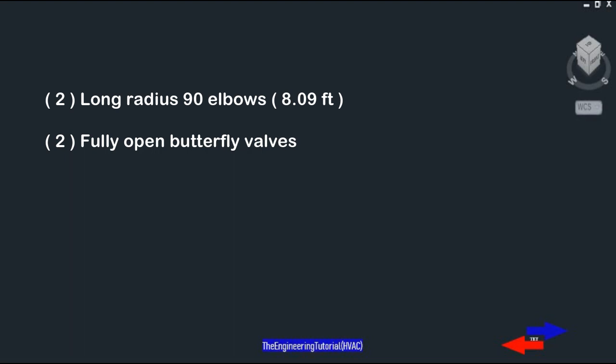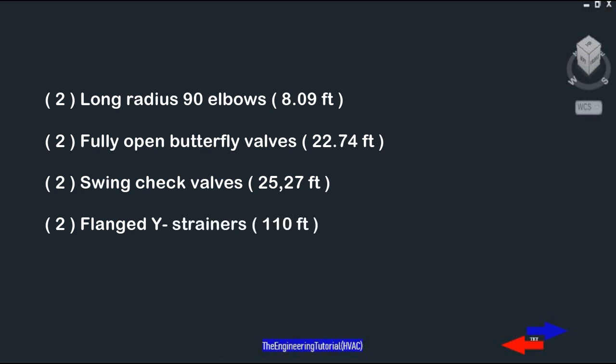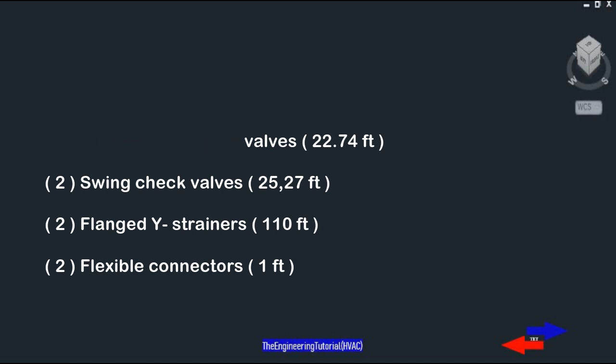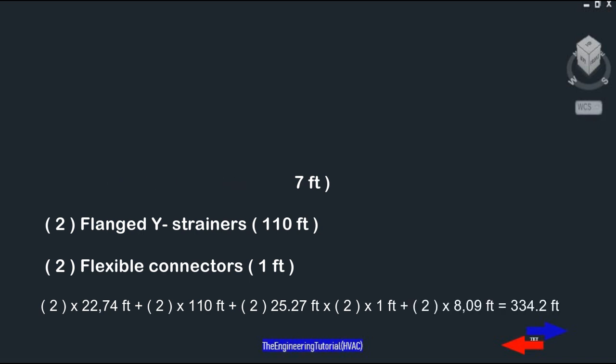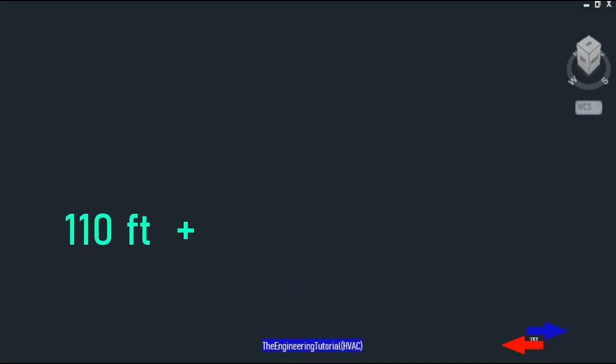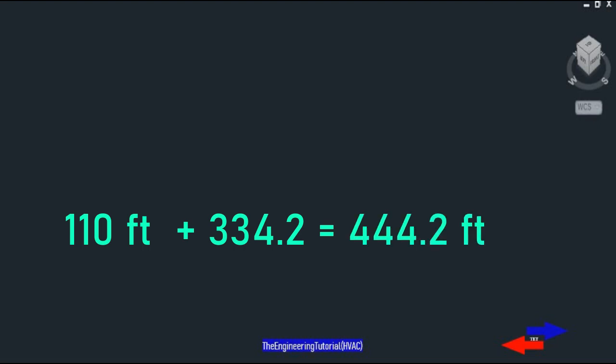We have two long radius 90-degree elbows, each with a pressure drop of 8.09 feet. Two butterfly valves, each with a pressure drop of 22.74 feet. Two swing check valves, each with a pressure drop of 25.27 feet. Two flanged Y-strainers, each with a pressure drop of 110 feet. Two flexible connectors with a pressure drop of 1 foot. Adding all these gives an equivalent length of 334.2 feet. Adding the 110-foot running pipe length gives a total length of 444.2 feet.